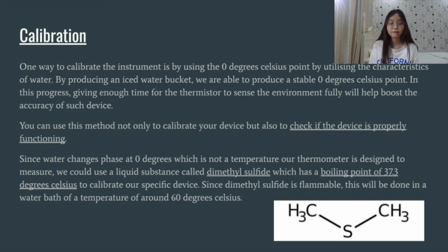You can use this method not only to calibrate your device, but also to check if the device is properly functioning. Since water changes phase at 0 degrees, which is not a temperature our thermometer is designed to measure, we could use a liquid substance called dimethyl sulfide, which has a boiling point of 37.3 degrees Celsius, to calibrate our specific device.